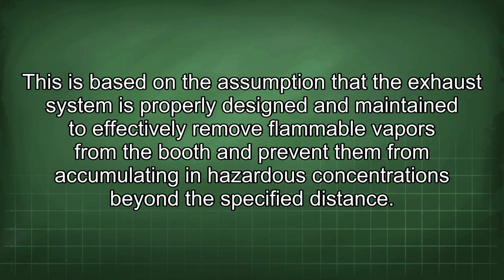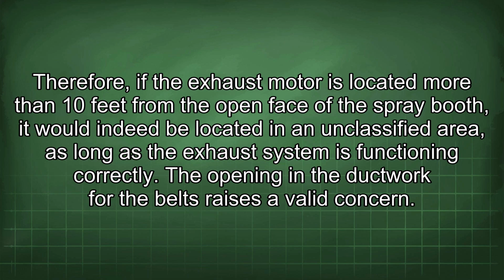This is based on the assumption that the exhaust system is properly designed and maintained to effectively remove flammable vapors from the booth and prevent them from accumulating in hazardous concentrations beyond the specified distance. Therefore, if the exhaust motor is located more than 10 feet from the open face of the spray booth, it would indeed be located in an unclassified area, as long as the exhaust system is functioning correctly.